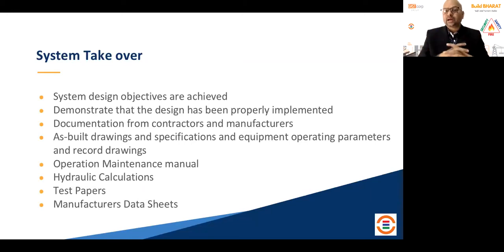Test papers - how have these fire doors been tested? Fire doors are very common, and it's a gray area for any facility: how do you ensure that a door is still rated as 30-minute or 2-hour? There is no way to authenticate this otherwise. Testing documentation is the only thing you can rely upon, along with the embossing on the fire door, which authenticates that the door is rated for, say, 2 hours, meeting your requirement.